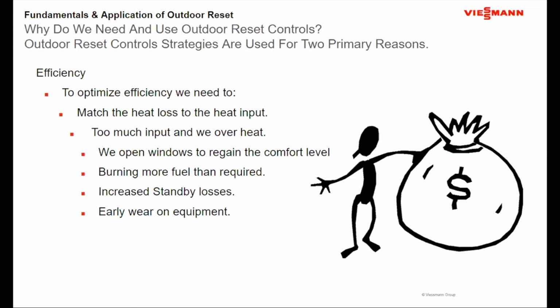And prior to doing a boiler with outdoor reset, you'd look at the apartment building and there'd be all kinds of windows in the building opened up a crack because the heat emitter was putting more energy into the building than the building was losing. So they had enough extra energy that they could lose more energy and still be comfortable in the building. Okay. When you do outdoor reset, you're putting the right amount of energy in that building, the windows go closed. You have really better comfort, but also better economy because you've now started to control the heat loss of the building.